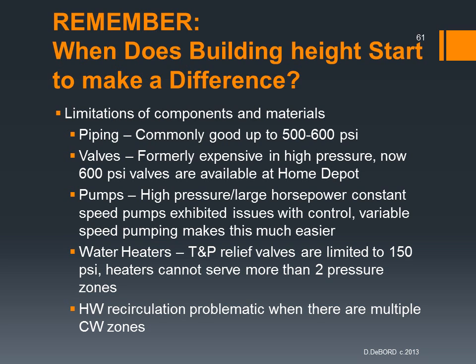The pumps, high pressure, large horsepower, constant speed pumps exhibited issues with control. Now we have variable speed pumping, which makes this much easier. I use variable speed for everything. Water heaters. The T&P relief valves are limited to 150 psi, so that can restrict you to 2 pressure zones depending on how you're feeding the system. Hot water recirculation is problematic whenever you have multiple zones, but we dealt with a lot of that in the previous materials.